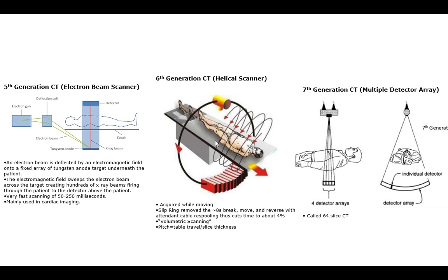So now I can have a continuous movement of the bed the person's on, and a continuous scan. So I make a helix as it's kind of going down along the bottom. Right? I never have a stop. I never change direction. I'm constantly moving in the transverse. There is no break. There is no reversal. There is no transit time. I'm taking it continuous with the system.